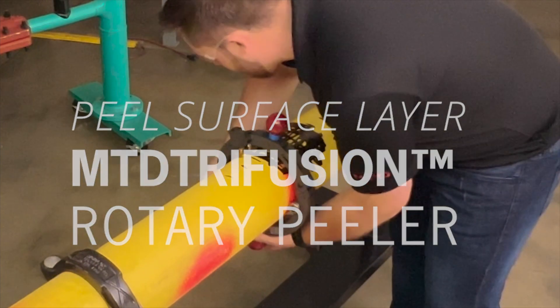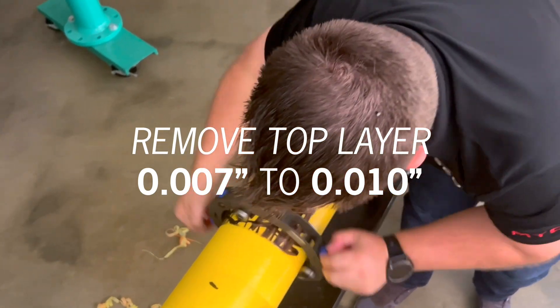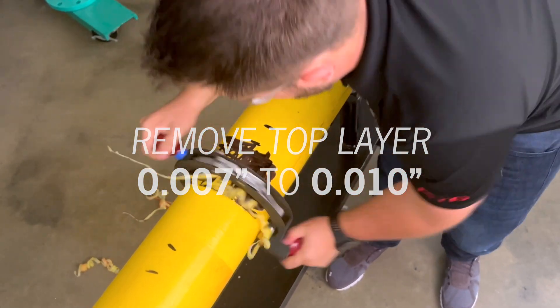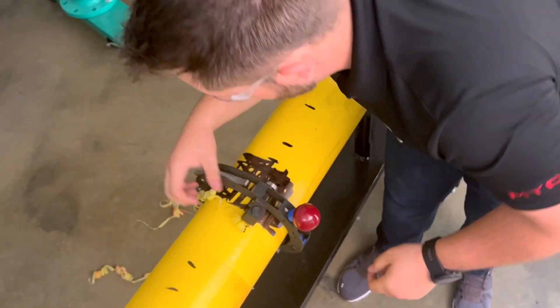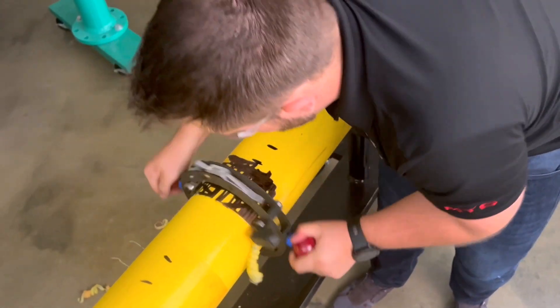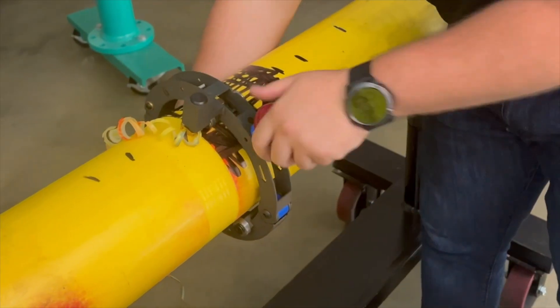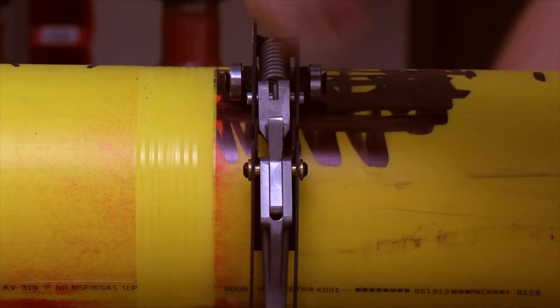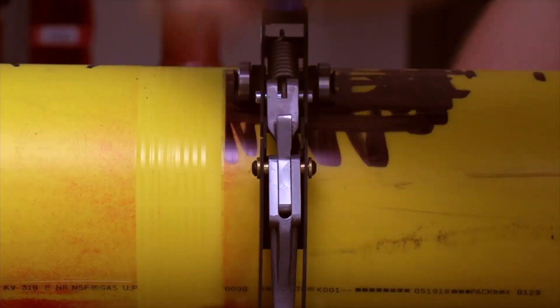Use a peeling tool to peel away the top layer of pipe surface. The peeler should remove at least seven to ten thousandths of plastic with each pass. If your peeler is removing less, it may not be working as it should. Ensure all witness marks are removed. We're using an MTD rotary peeler. The rotary peeler is quick and easy to use and consistently removes the required amount of material.